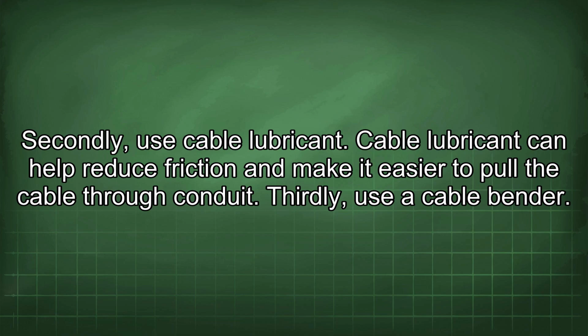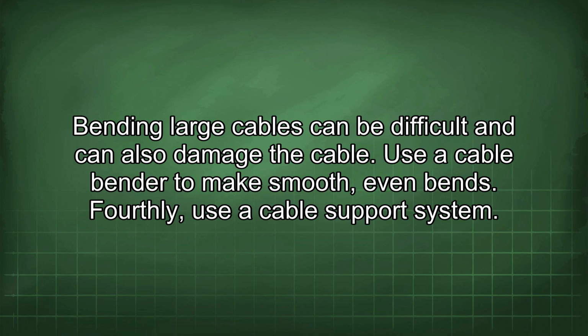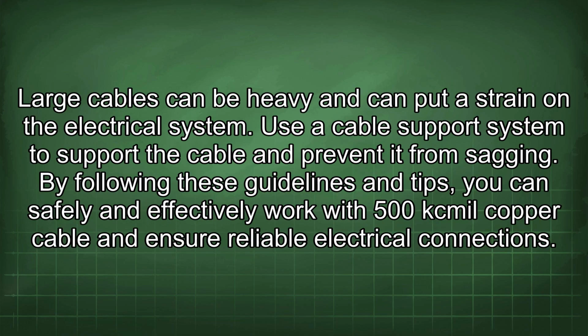Thirdly, use a cable bender. Bending large cables can be difficult and can also damage the cable. Use a cable bender to make smooth, even bends. Fourthly, use a cable support system. Large cables can be heavy and can put a strain on the electrical system. Use a cable support system to support the cable and prevent it from sagging.